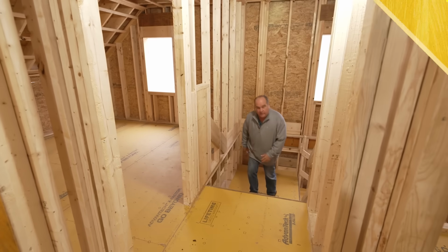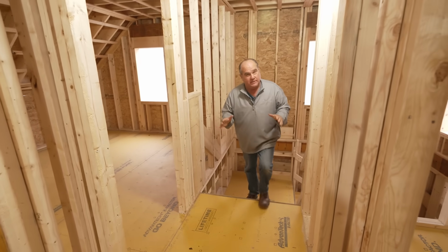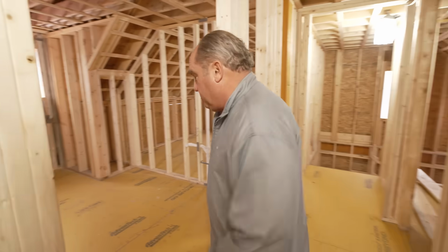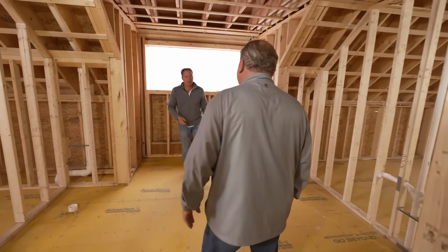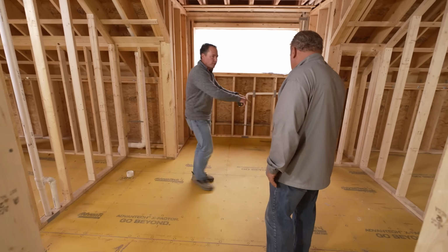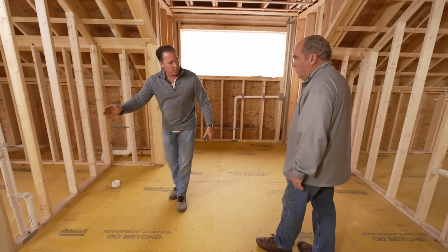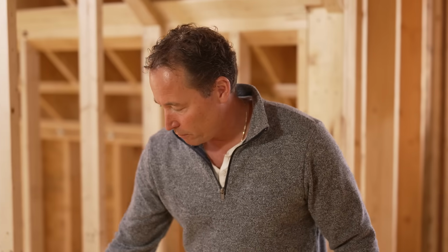So we have reached the point in our project where it's time for the HVAC and the plumbing teams to figure out exactly where they're going to fit ducts and pipes in this building. And that's always a challenge, Brian, isn't it? It is, Richard. Yeah, we had some LVLs in the floor that came across over here and one across over here, which really restricted me from getting any drain work from over here across. So individually had to vent the shower and the toilet.